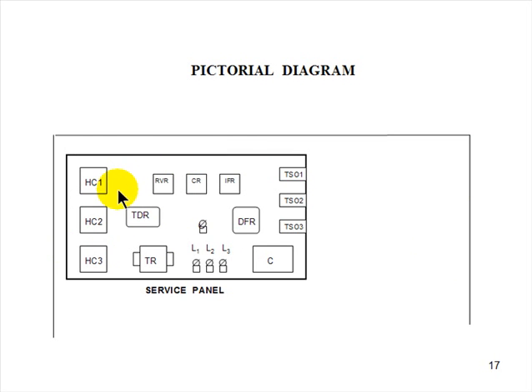Pictorial diagrams simply show you a picture of where the controls are in the system. If you open the door to a complicated device and they have a pictorial diagram, and you're looking for the reversing valve relay, oh, it's right up top. There are 3 relays together. It's the one on the left. That's how you would find it. You want to know where the defrost relay is? Oh, it's right below that stack. Where's the contactor? Oh, it's in the bottom right corner of the control panel. Where's the second outdoor thermostat? Oh, it's on the right here between these two. That's all it's for. It doesn't tell you when the reversing valve relay is energized. It just tells you where it's located in the system.